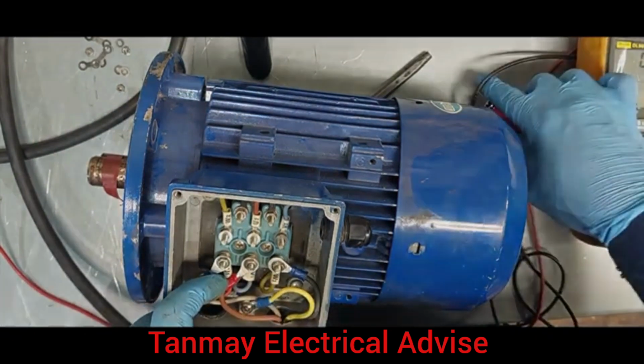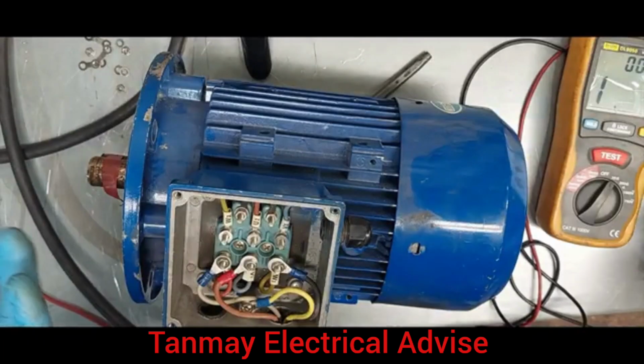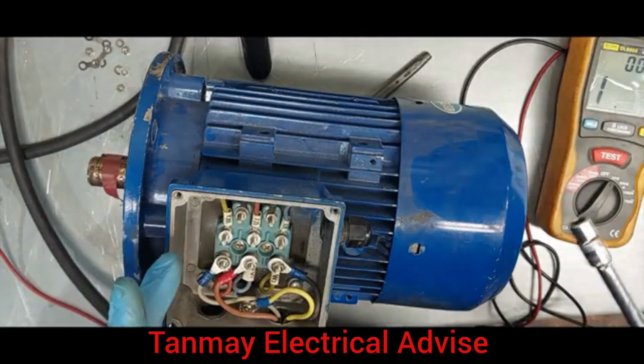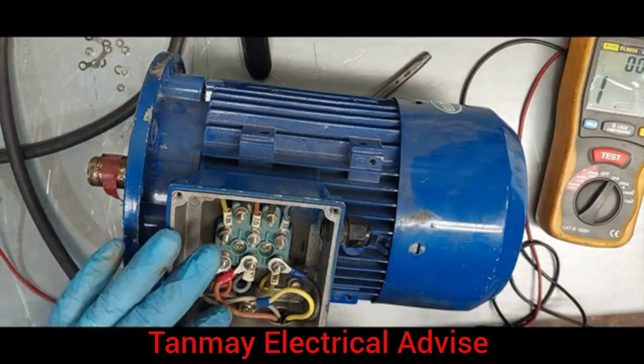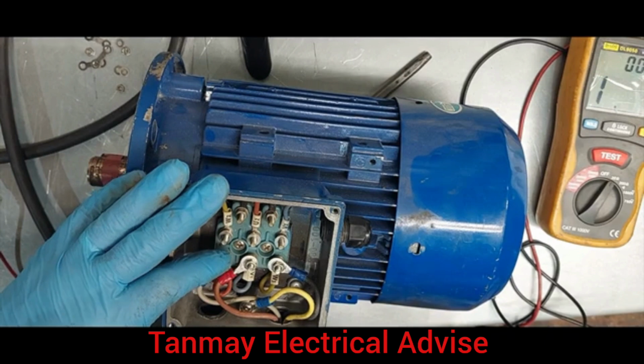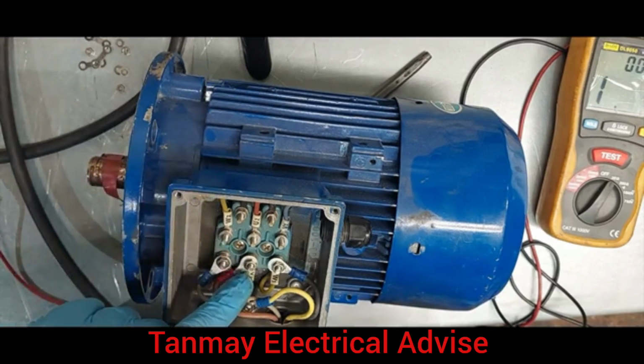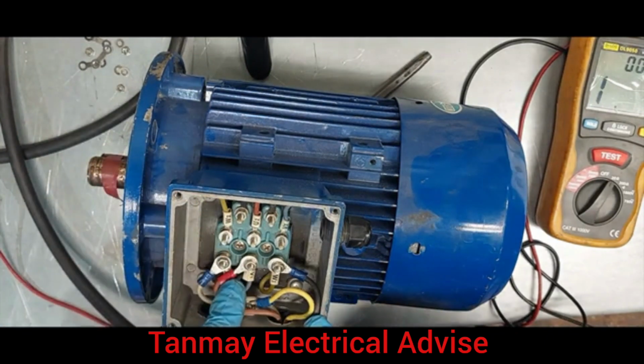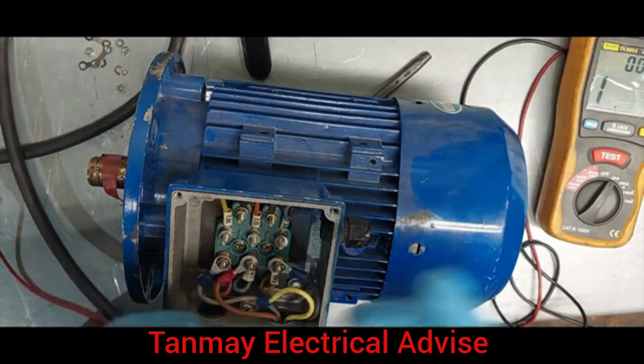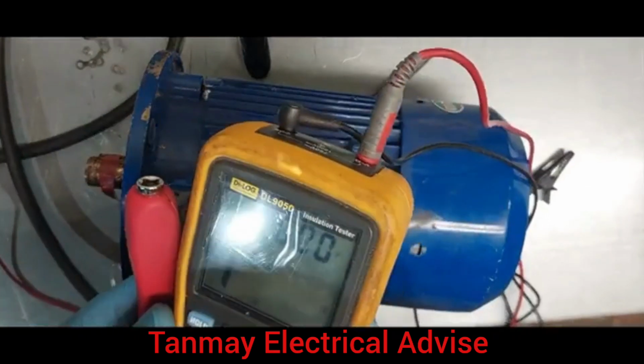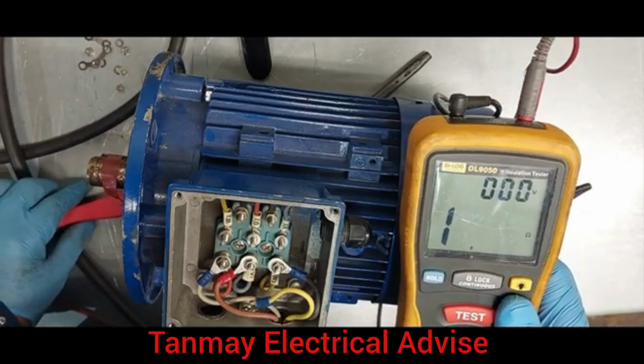The next thing to do now, we're going to do the final test, which is the insulation test. During the insulation test, we will be injecting high voltage into the windings of the motor. The high voltage output of the insulation resistance tester will search out and indicate any weakness in the insulation of the windings or cable.